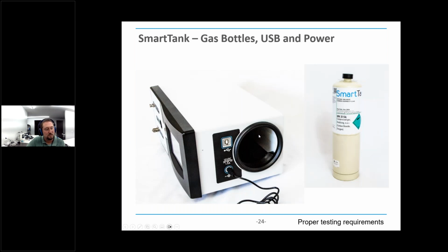On the side of the SmartTank is a place to put the gas bottles. They slide into the device. That's most of the volume of this device, is actually protecting the bottle. You change the bottles out based on the device you're testing. You've got a USB port, which allows you to download reports from the device, which it makes automatically. There's a power plug. You can run it off power, or there's a battery that will run all day, at least 8 hours on a full charge.